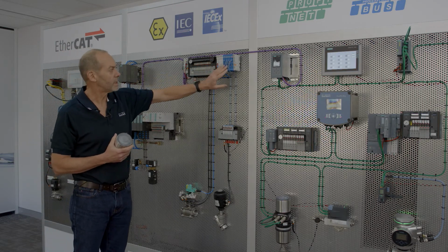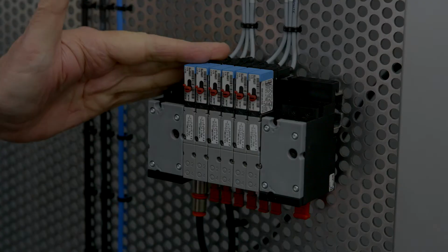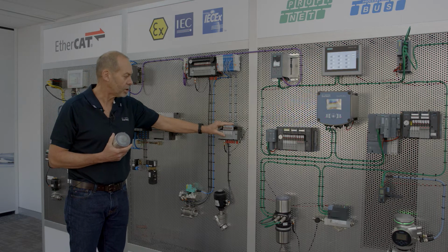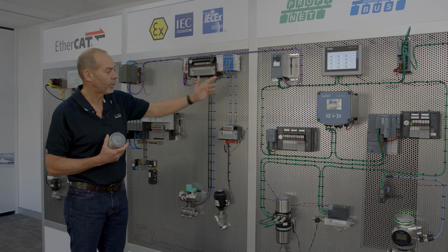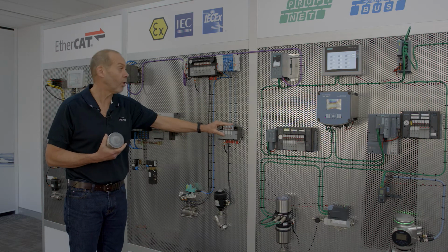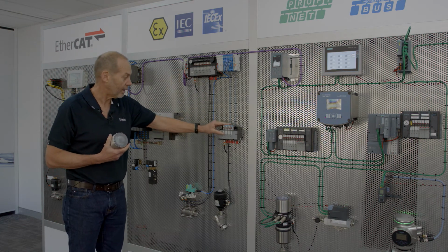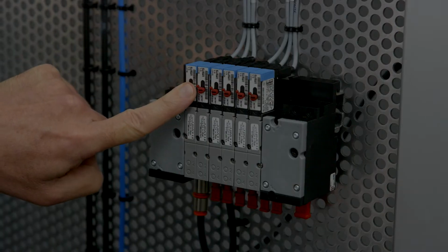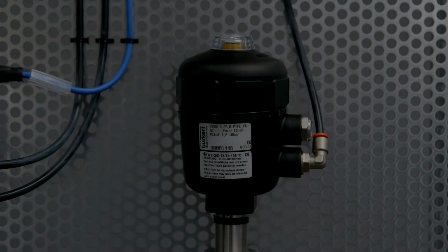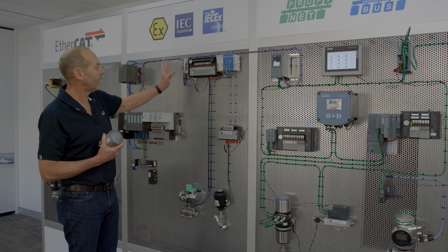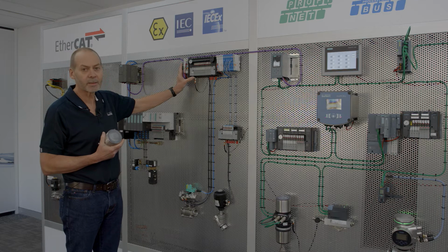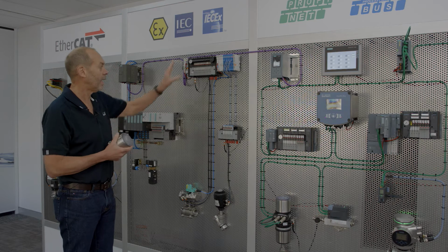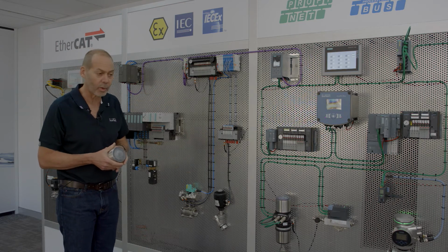You can also use this system to mount your valves directly in the field, in the Zone 1 area. Bürkert has a range of intrinsically safe valves which can mount directly through these barriers, so they can go onto that same network. These valves can be mounted directly inside that area, along with the valves that they're operating. If you had a distributed or centralized system, this is the most ideal way of connecting in a Zone 2 area and then taking your devices into a Zone 1 area.